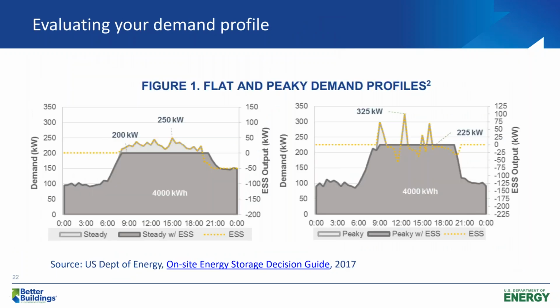Thinking about your own demand profile is very important. How peaky your demand profile is makes a difference in how much demand is reduced with the same size of storage. In the first figure, we're reducing peak demand from 250 to 200 kW for this pretty flat profile. That same amount of storage can reduce the example on the right from 325 kW to 225 kW, because it's more peaky and you're not using that storage as consistently over that time frame.